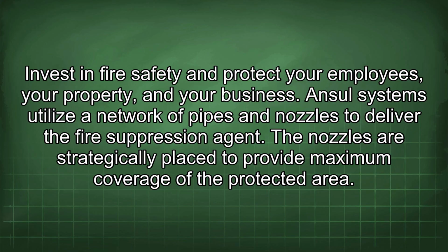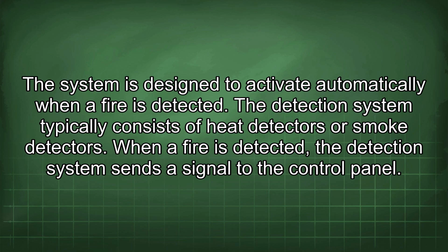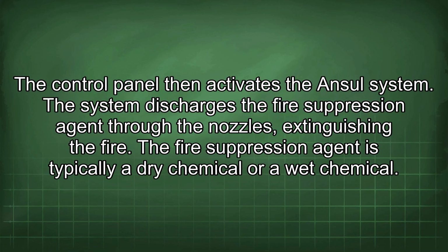Ansul systems utilize a network of pipes and nozzles to deliver the fire suppression agent. The nozzles are strategically placed to provide maximum coverage of the protected area. The system is designed to activate automatically when fire is detected. The detection system typically consists of heat detectors or smoke detectors. When a fire is detected, the detection system sends a signal to the control panel. The control panel then activates the Ansul system. The system discharges the fire suppression agent through the nozzles, extinguishing the fire.